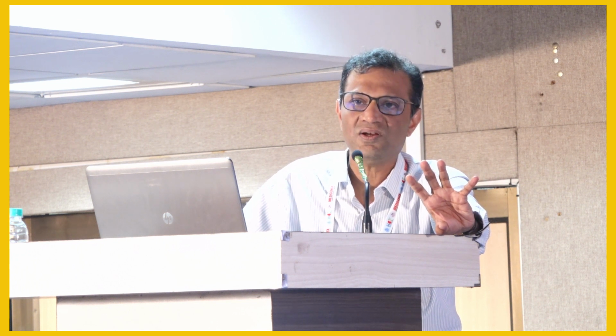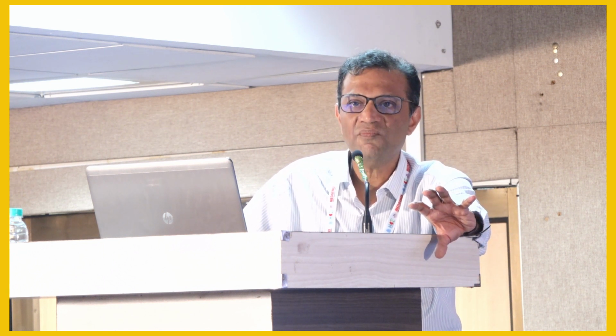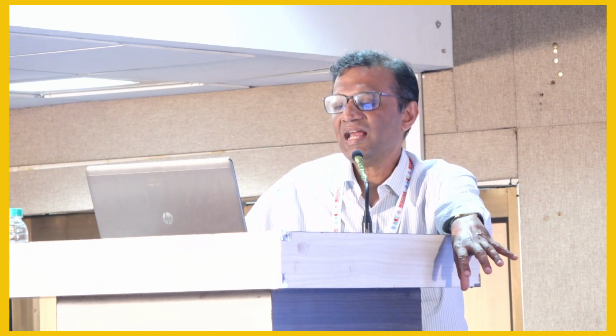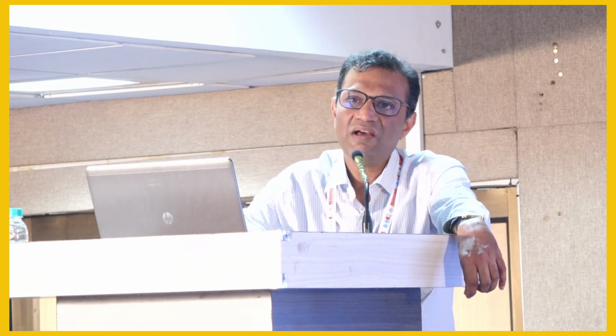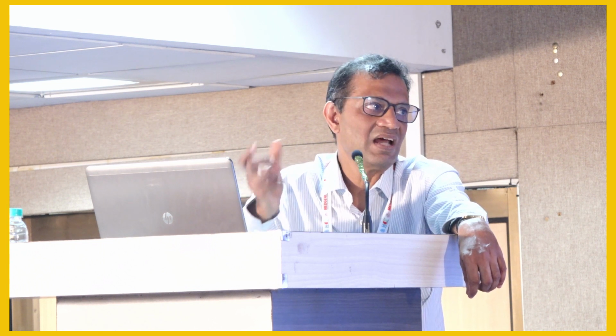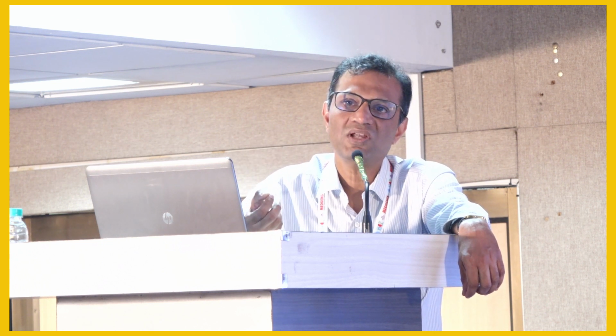And this is the diaphragm which moves, and so at any given time, the diaphragm ensures that while one side is discharging fresh dialysate to the dialyzer, the other side is filling with fresh dialysate from the mixing chamber. In the next stroke of the cycle, the fresh dialysate which has come from the mixing chamber goes to the dialyzer, and spent dialysate from the dialyzer will come back to the chamber. So, the next stroke of the pump will never happen unless the chamber is balanced, unless an equal volume of fresh dialysate has been delivered to the dialyzer and come back from the dialyzer, the machine will not move to the next stroke of the pump.